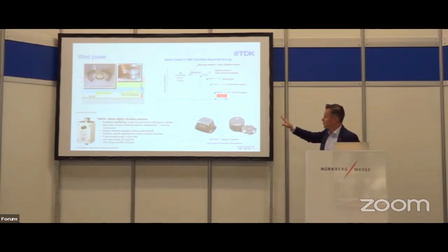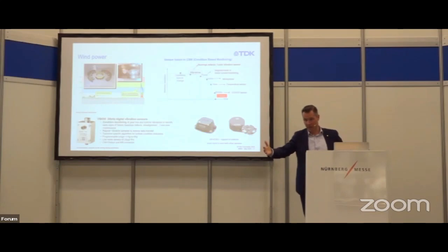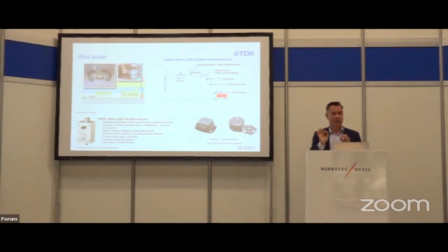To do that, you need a high frequency vibration sensor. It's not sufficient to have a 2 kilohertz vibration sensor. You really need to go up to 10 or 20 kilohertz to detect the fine differences from normal behavior.